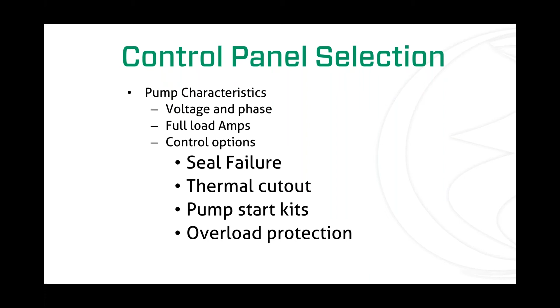By selecting the pump for your application first, it's going to give us things like the full load amp draw. That's going to make sure we get the right wiring size and right components built into the panel for you. The pump you might select may have options on it, such as a seal fail circuit. It might require external thermal cutout protection, or need overloads and components such as that. All of these things will need to be taken into consideration when selecting a control panel. Again, it is not one size fits all.